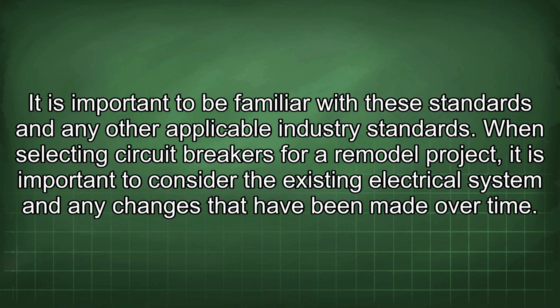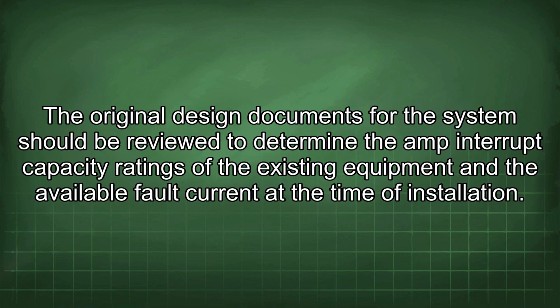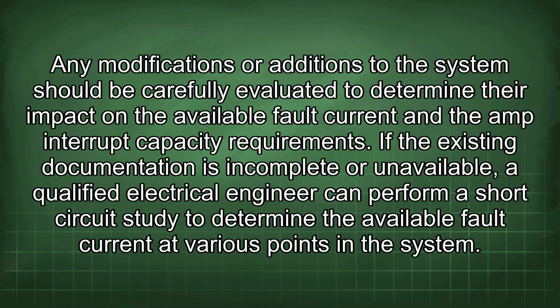When selecting circuit breakers for a remodel project, it is important to consider the existing electrical system and any changes that have been made over time. The original design documents for the system should be reviewed to determine the amp interrupt capacity ratings of the existing equipment and the available fault current at the time of installation. Any modifications or additions to the system should be carefully evaluated to determine their impact on the available fault current and the amp interrupt capacity requirements.